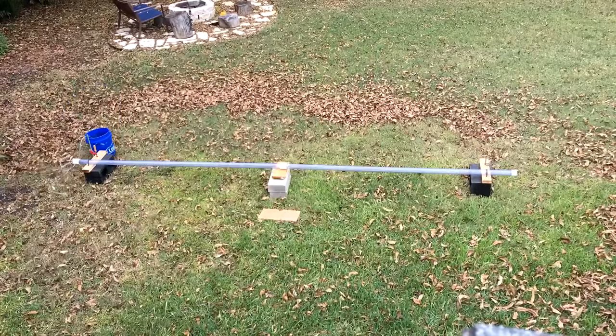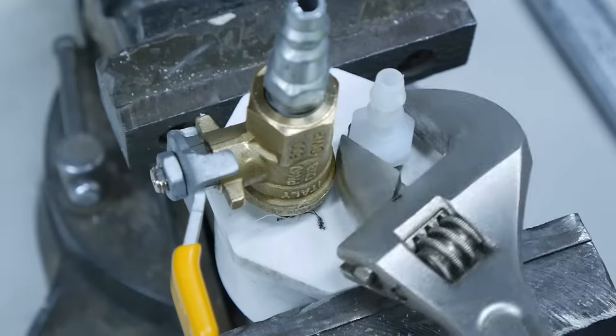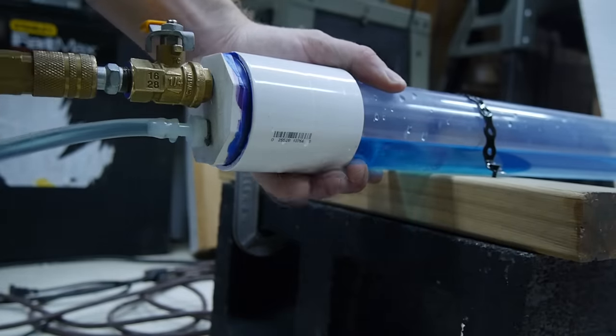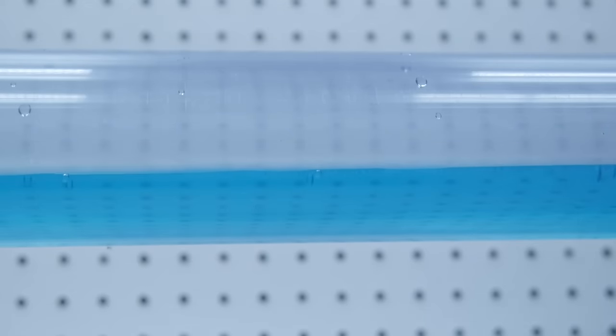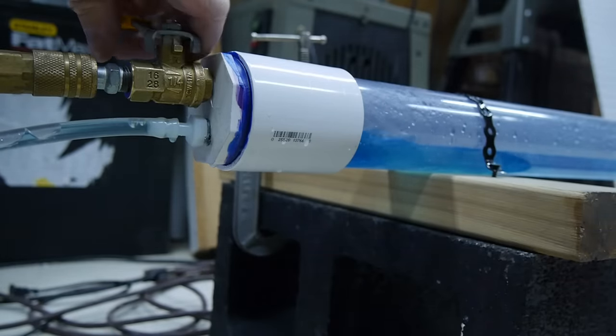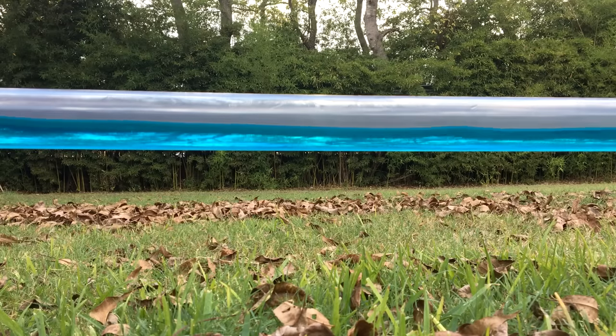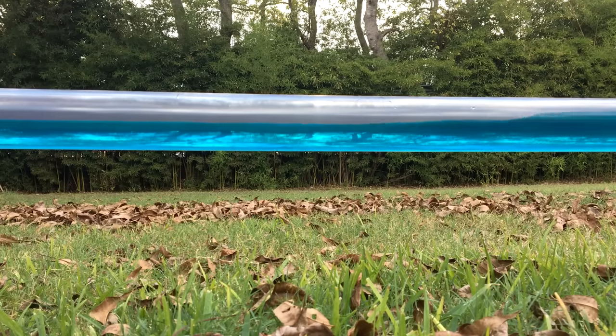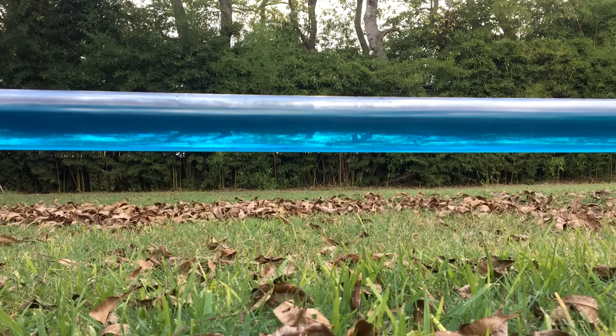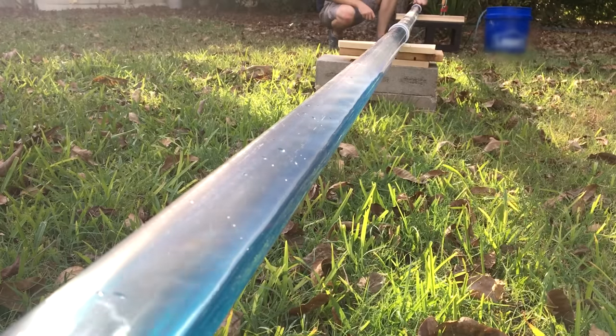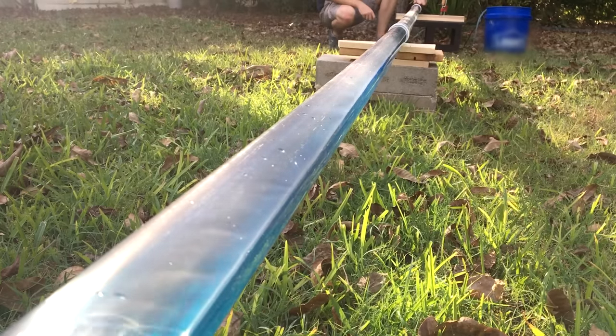But to show how it works, first we need a steam pipe. Condensation in a steam pipe is always occurring just from normal transfer of heat to the outside air, and this is roughly what that might look like. I'm using compressed air here in lieu of steam for the obvious safety implications. Engineers manage this condensate by sloping steam pipes and by installing devices that can get rid of condensate from the pipes, called steam traps. Steam traps are a fascinating topic on their own, but occasionally they get clogged or malfunction, allowing condensate to build up. When water and steam flow together in the same pipe, it's known as two-phase flow.